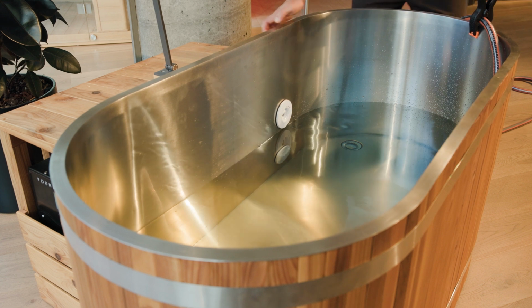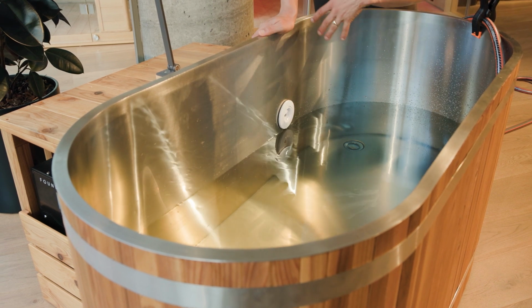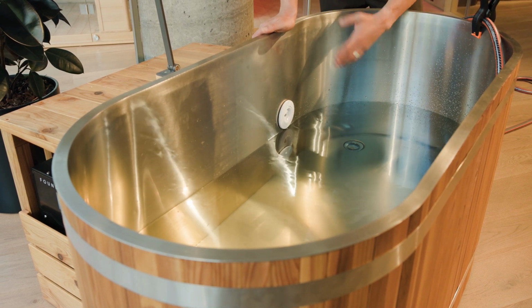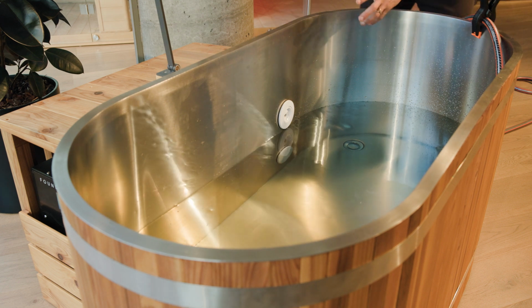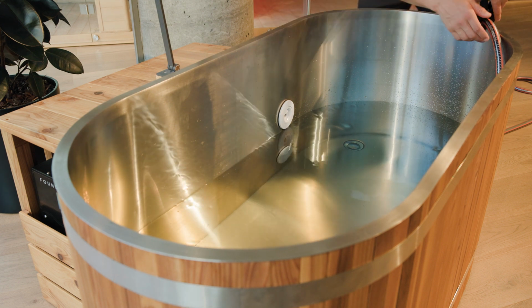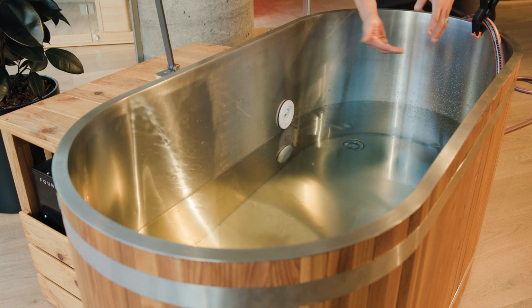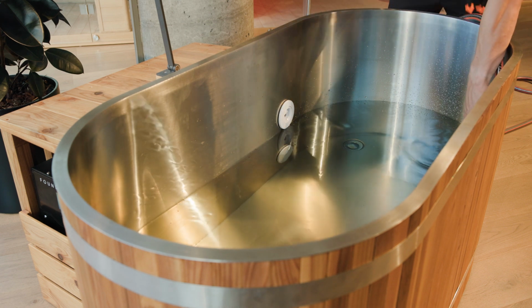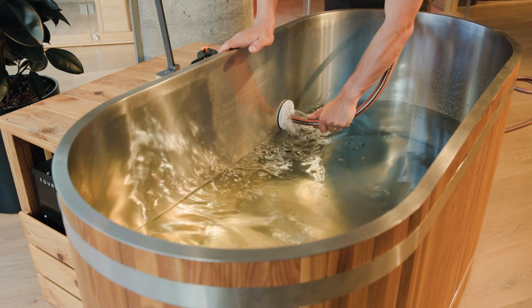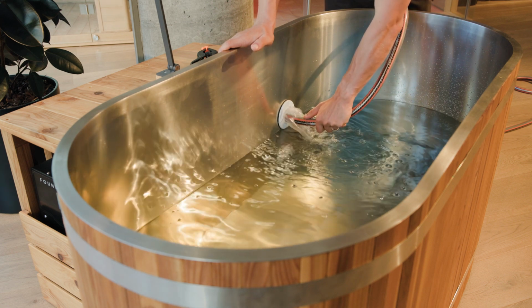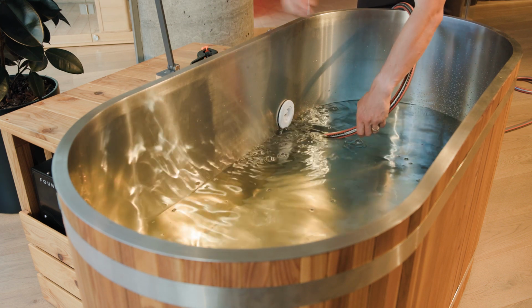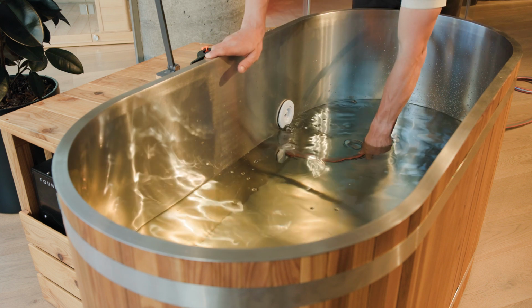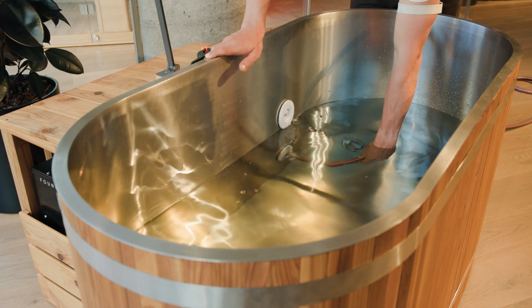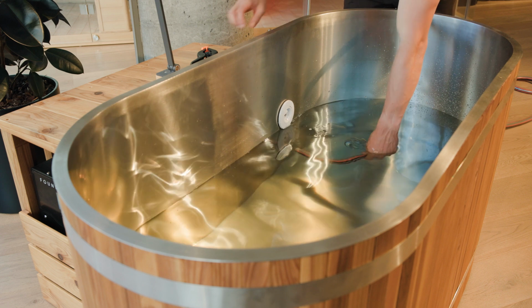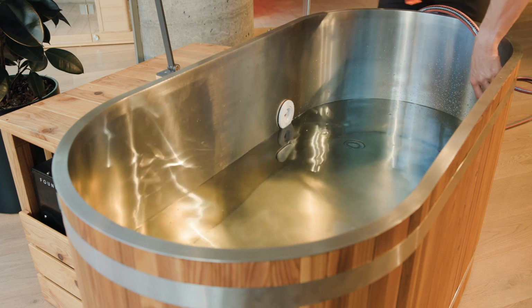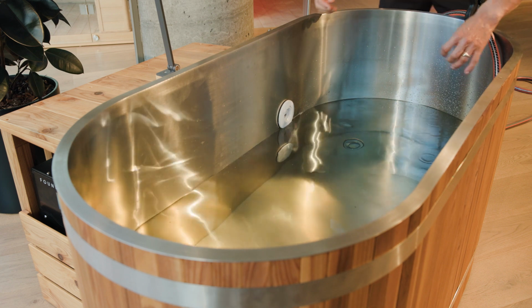Sometimes at this phase, when we turn the chiller on for the first time, it may need to be primed. That's because when we change the filter, an airlock can sometimes be created inside the chiller, so we turn it on but it doesn't start pumping out water. The way to remedy that is to send the hose into the top inlet, which fills the chiller with water from the top and helps it prime. Sometimes we may also need to put extra water in the bottom, which also gets water into the chiller and helps clear out any airlocks.